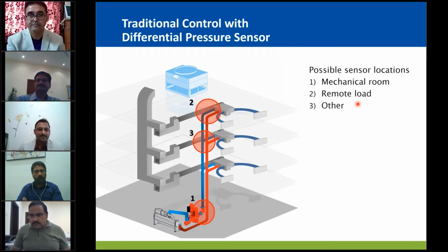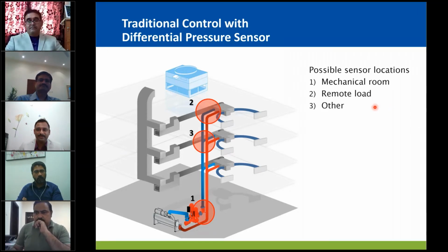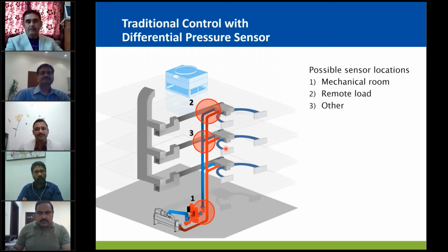Now that's the best practice, but it's often seen as a difficult place to install, and more often we see the sensors going into the plant room. Now that could be another sensitive load in that building. It could be a server room, or instead of putting in a remote zone, probably they have a high pressure drop area, and we want to put the sensors in that particular location as well.